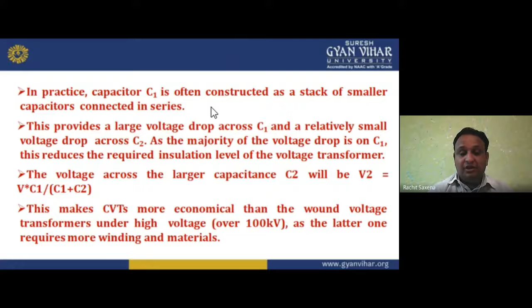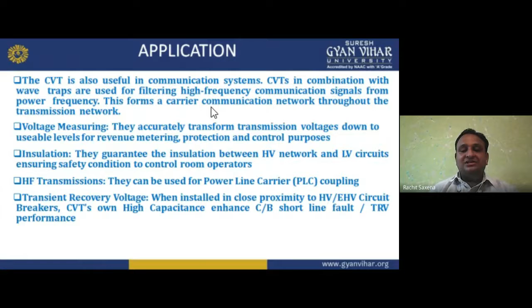Now applications. A CVT is also useful in communication systems. CVTs in combination with wave traps are used for power line carrier communications, for filtering high frequency communication signals from power frequency. This forms a carrier communication network throughout the transmission network we have. Voltage measuring we can do. They accurately transform transmission voltage down to usable levels for revenue metering, protection and control purposes. Insulation: they guarantee the insulation between the high voltage network and the low voltage circuit, ensuring safety conditions for control room operators. High frequency transmission: they can be used for power line carrier communication, that is PLCC, coupling. Transient recovery voltage: when installed in close proximity to HV and EHV circuit breakers, CVTs with high capacitance enhance circuit breaker short line fault, or TRV, performance. So these are the applications.